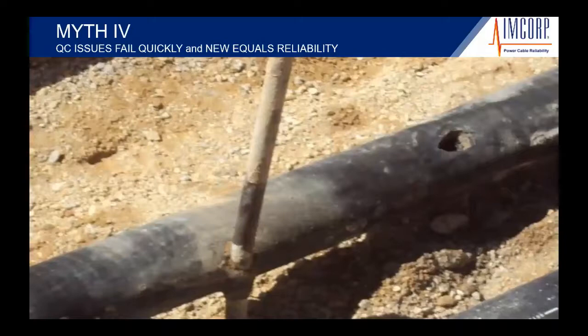So even though it was a nasty installation, this cable was able to operate in the field for well over 2.5 years. So if we take a look at the water trees and the electrical trees, and then a bad installation, we start forming an opinion that cables take a while to break down. It's an erosion process of the insulation to create a carbon path from the inner conductor to the outer conductor called a failure.